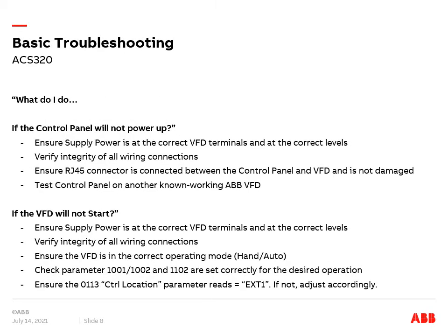You might ask yourself some of the following questions while troubleshooting an ACS-320. What do I do if the control panel will not power up? Ensure the supply power is at the correct VFD terminals and at the correct levels. Verify the integrity of all your wiring connections. Ensure that the RJ45 connector is connected between the control panel and the VFD and is not damaged. And test the control panel on another known working ABB VFD.